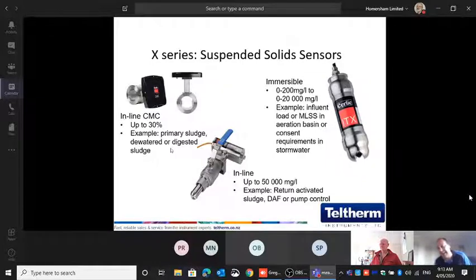And lagoon sludge is black. As soon as black passes, the unit can't transmit the light anymore. So they had to go to microwave units. Microwave units can measure up to 30%. It's a different technology, microwave, but we can go up to 30%. If you want to go higher, we have other near-infrared units, but they're not much used at the moment.